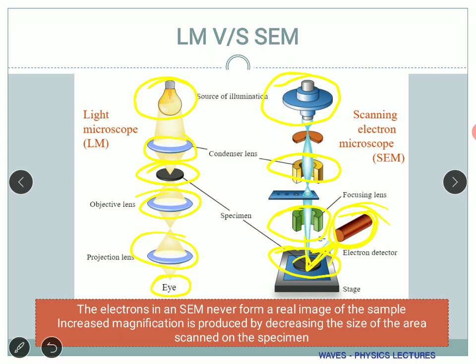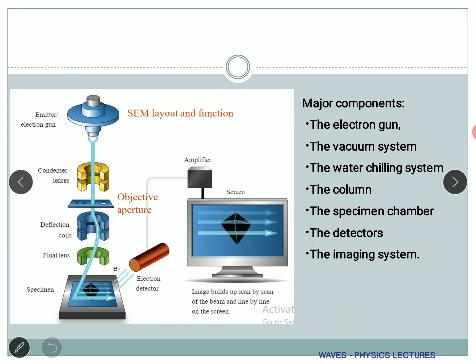You have to remember that the electron in an SEM will never form a real image of the sample. When we look through a microscope we are looking at a real image, but here it is basically a representation. Depending on how many backscattered electrons are accumulated in the detector, that sends an image — giving a sense of depth. Increased magnification is produced by decreasing the size of the area scanned on the specimen, so we can keep changing magnification depending on need.